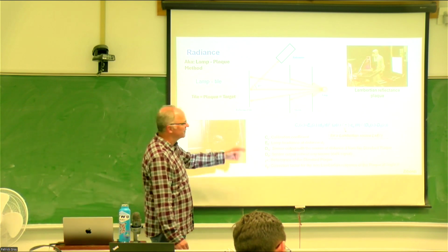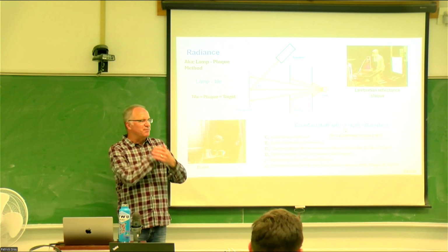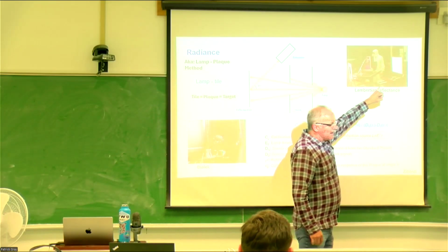It's probably no longer a Lambertian reflector, which is what's required to do this. If you bump your instrument against it by accident and it gets a dent, you send it back to the company and they resurface it. They take off enough thickness of the material so that the dent is gone. This thing can cost up to $15,000. So expensive.